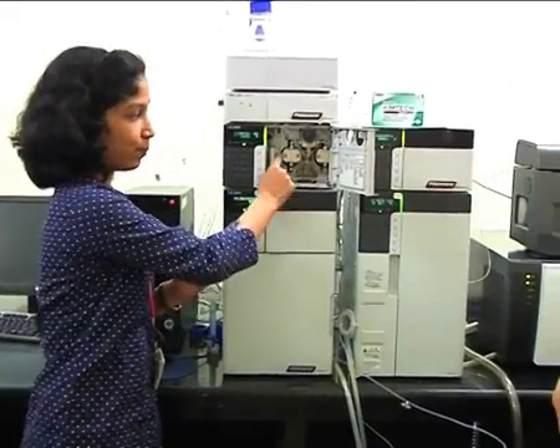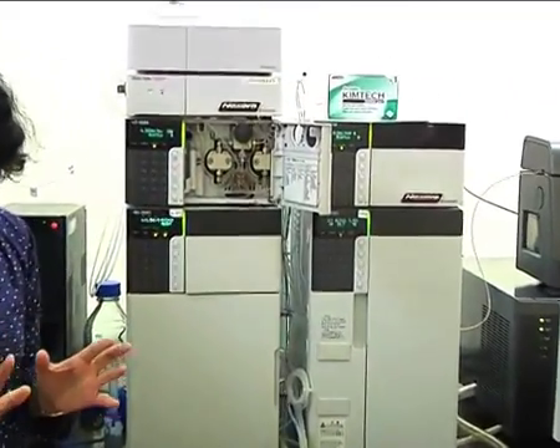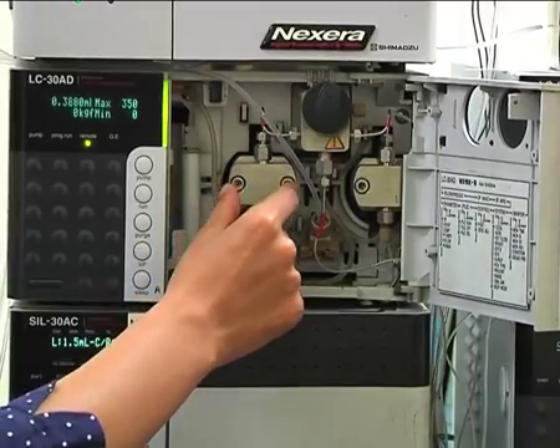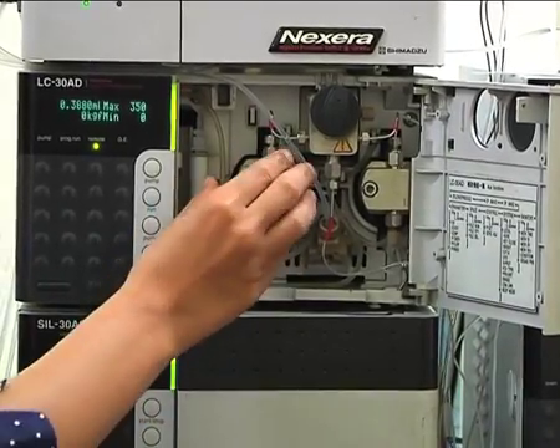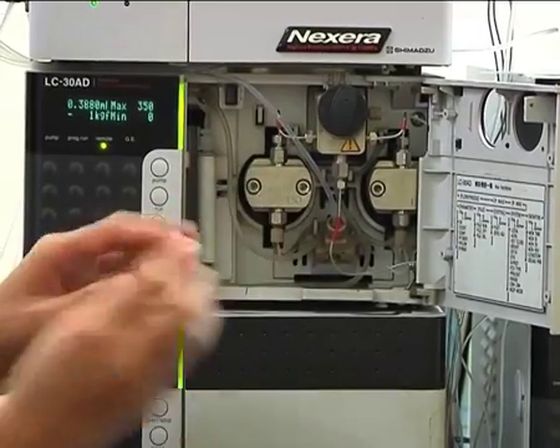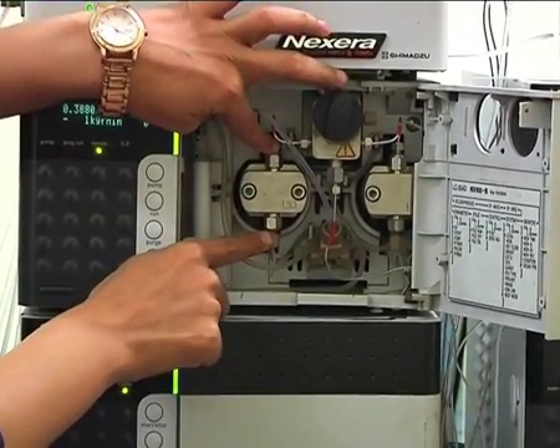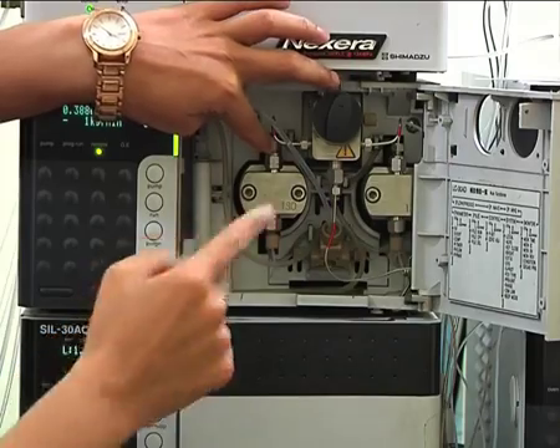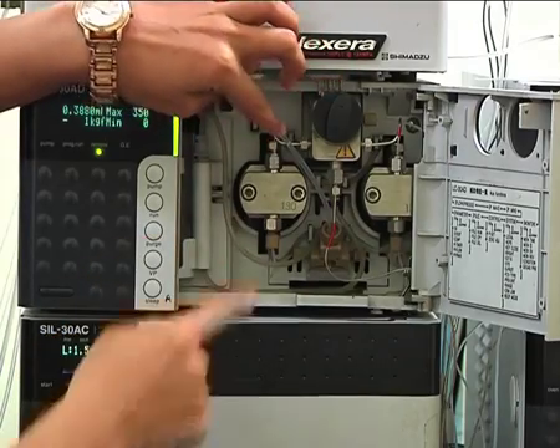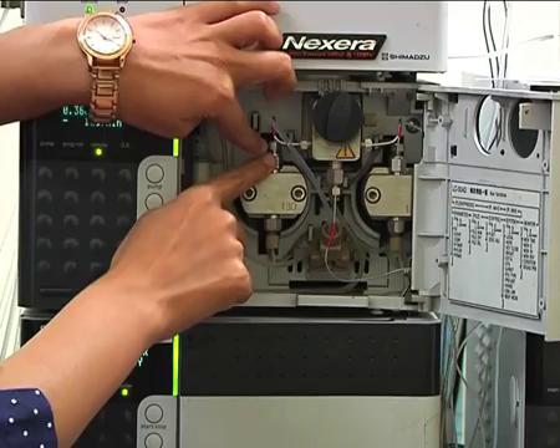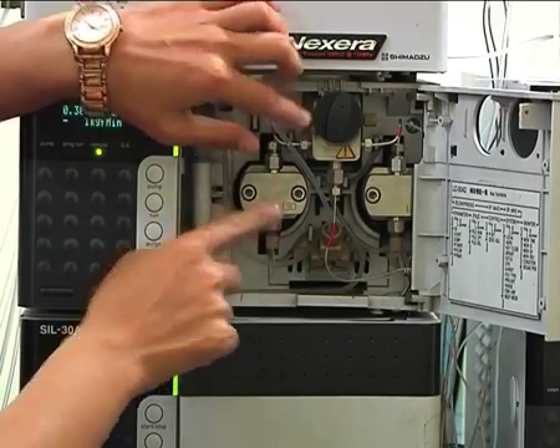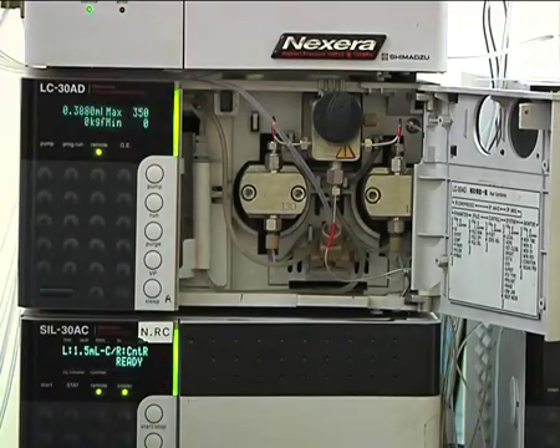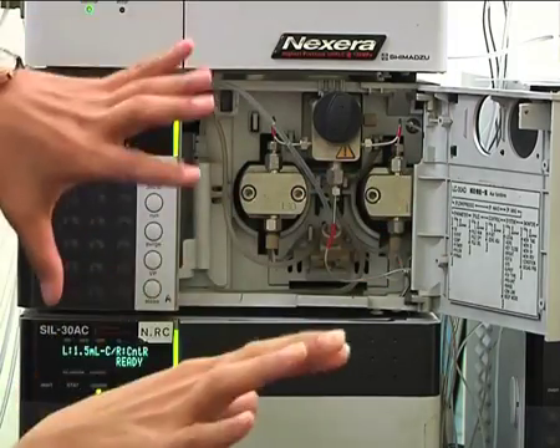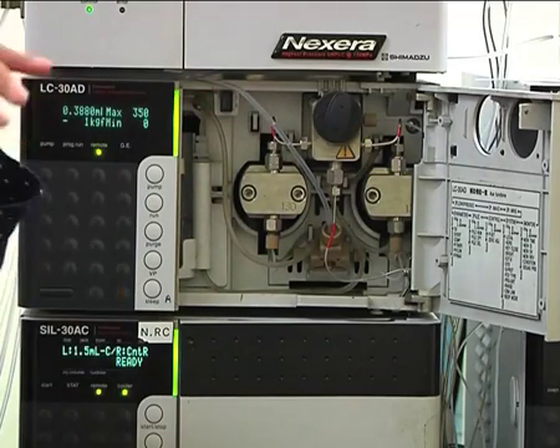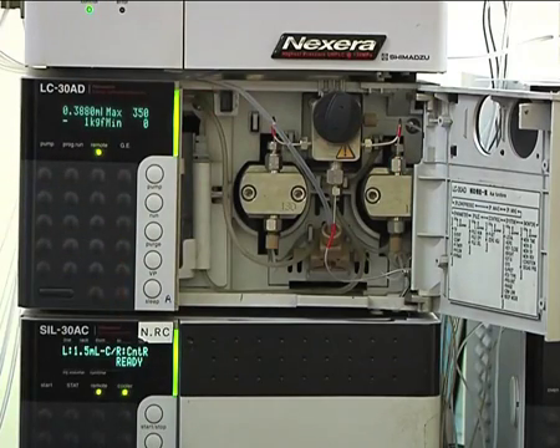Now here you see a dual plunger reciprocating kind of pump. This is the plunger unit, where the mobile phase gets stored. These two are check valves. These two are non-returnable check valves. That means when this valve is open, this will be closed, and when this is open, this will be closed. This ensures that the flow of the mobile phase will be unidirectional. If both ends are open at the same time, half of the flow might go this way and half might go that way. We don't want this scenario.